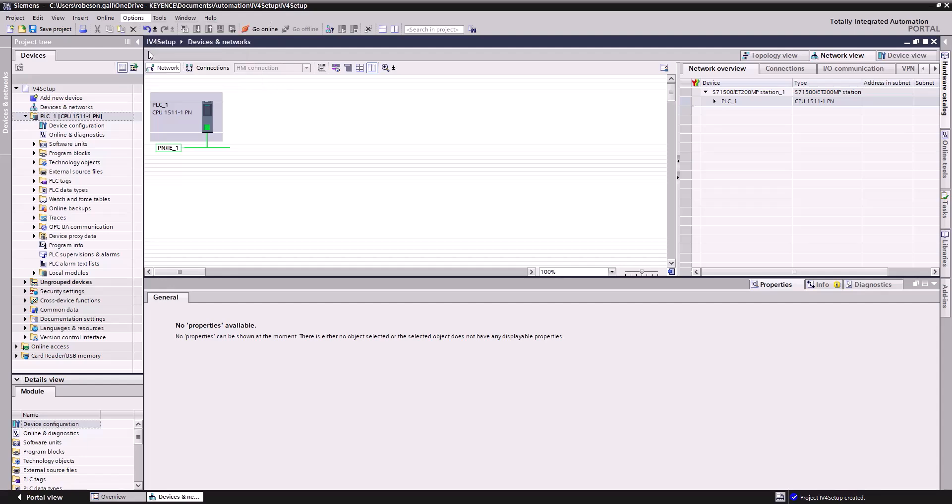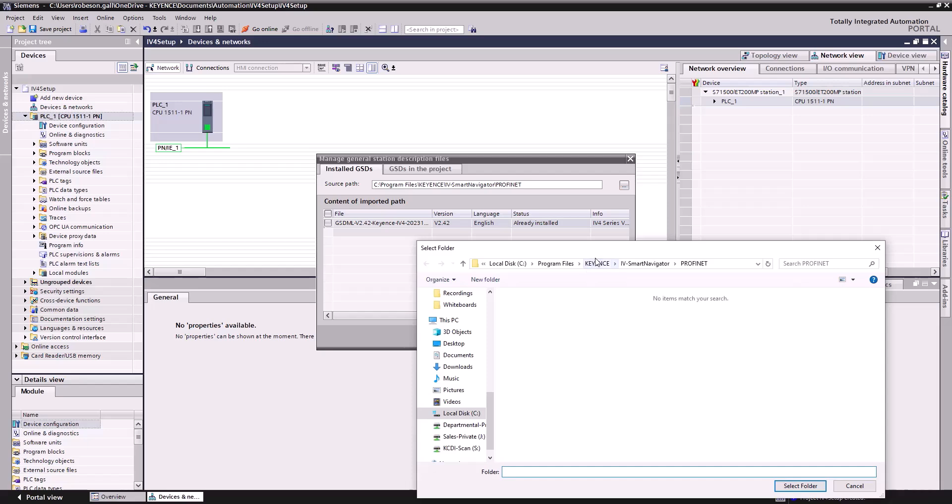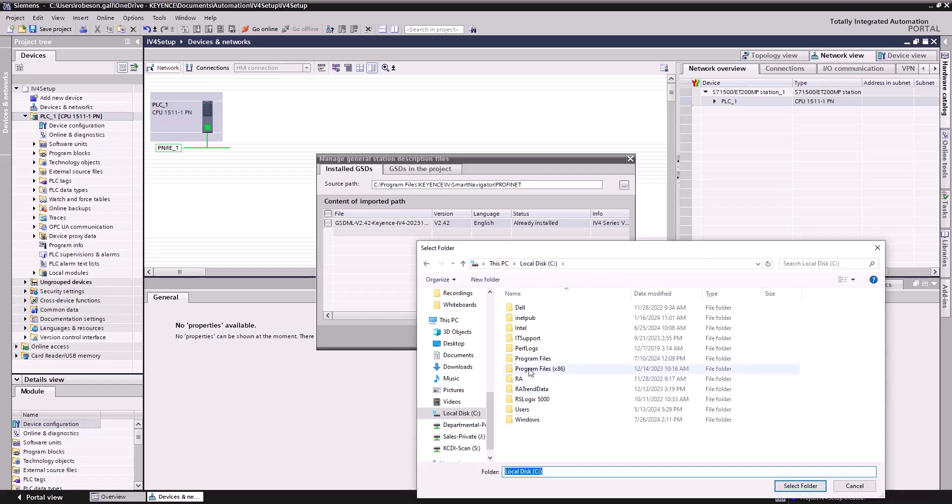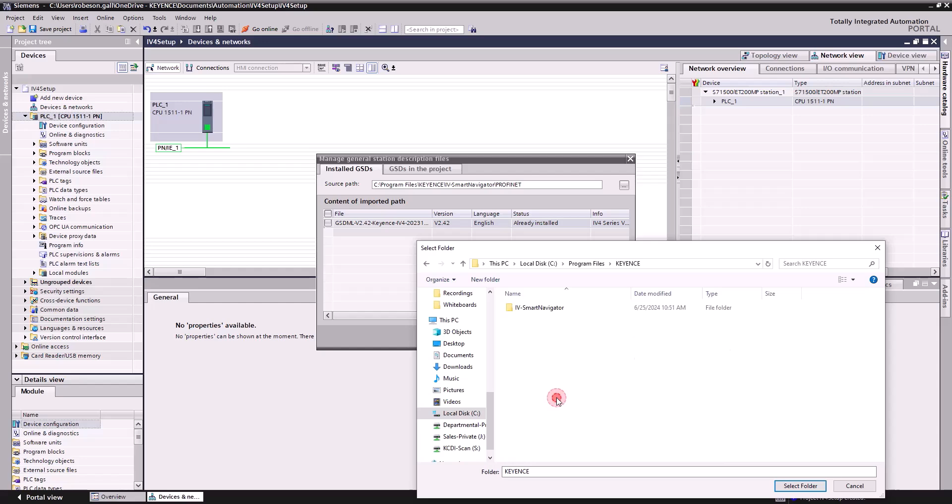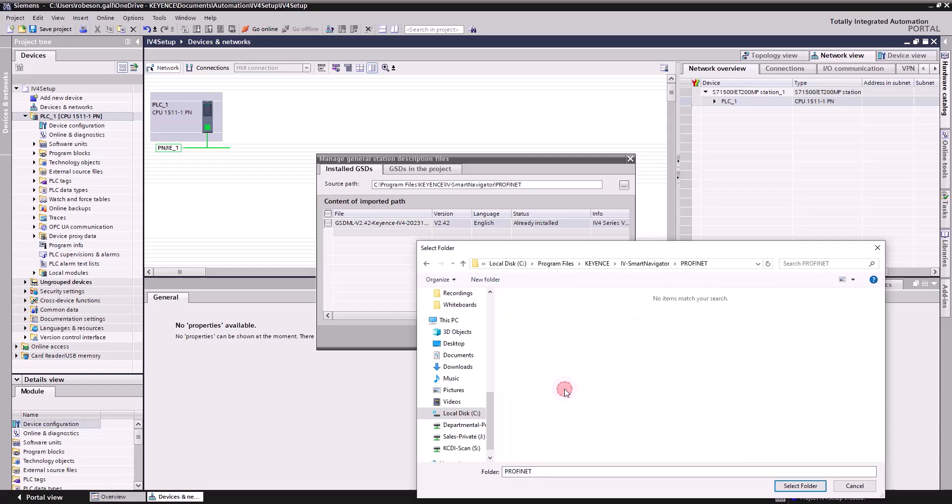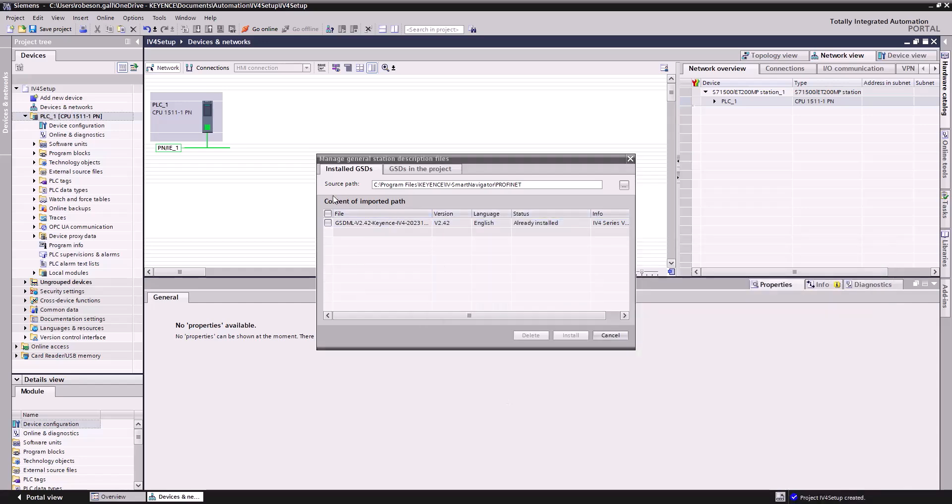To do this we'll go to options, manage general station description files. And you'll see I've actually already imported my IV4 GSDML file. What's nice with the IV4 now is when you actually install IV Smart Navigator software to use this, you can see where I get my source path from. This will be C drive, program files, Keyence, IV Smart Navigator, and then in this PROFINET folder. But the contents of that folder contains this GSDML file for the Keyence IV4. So you can just use that. It's going to already be on your computer if you have the software installed.